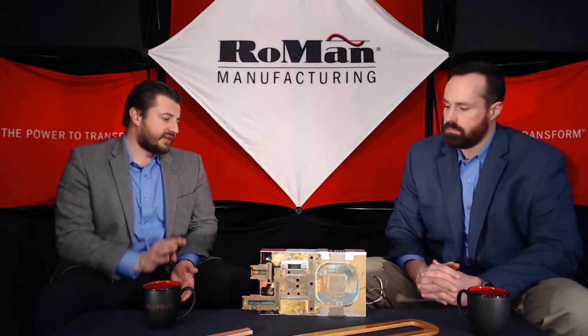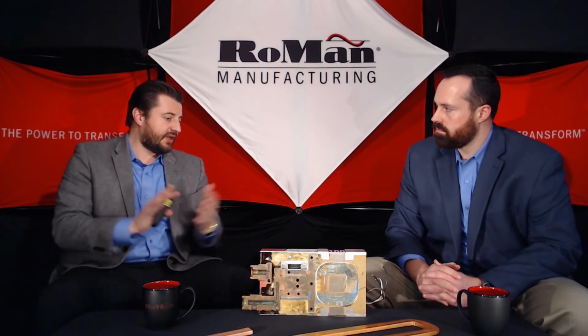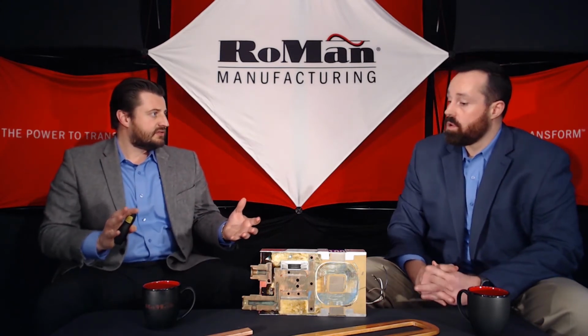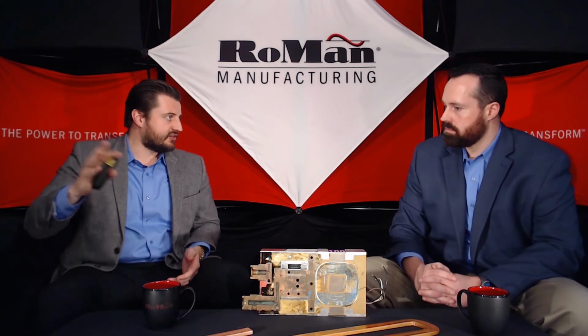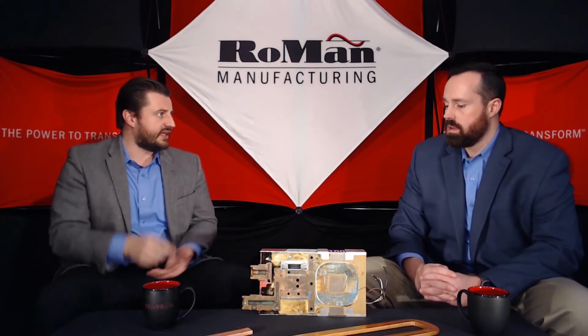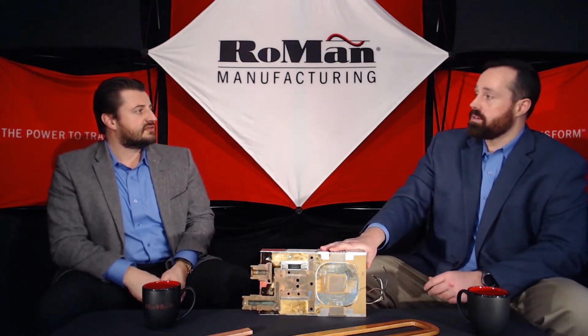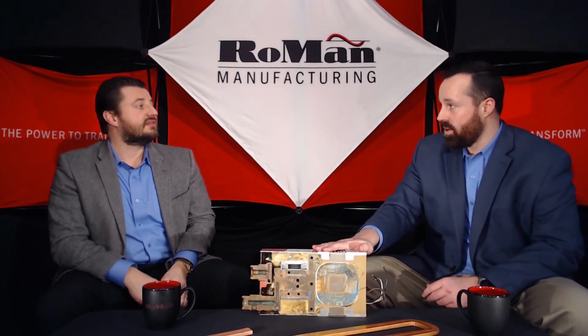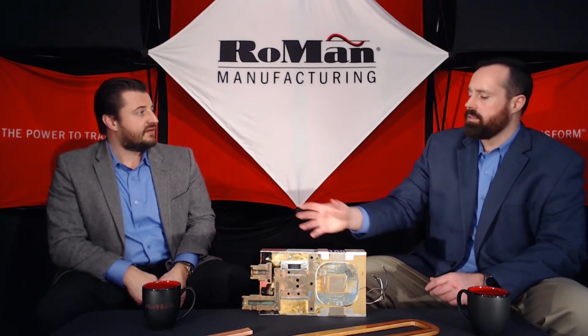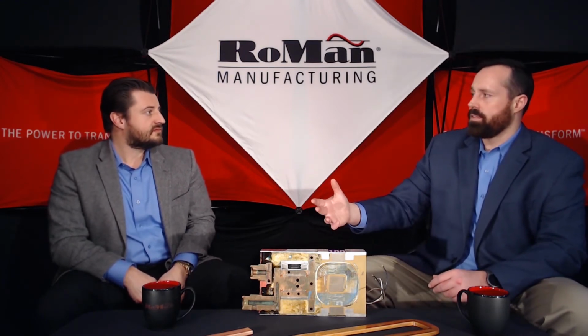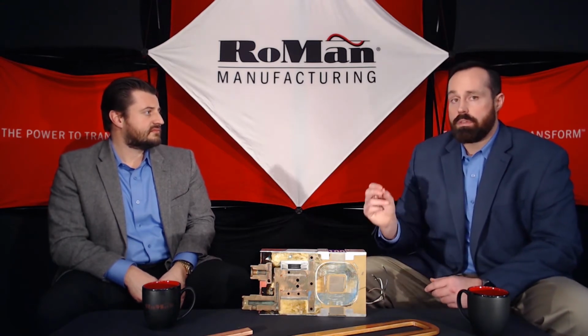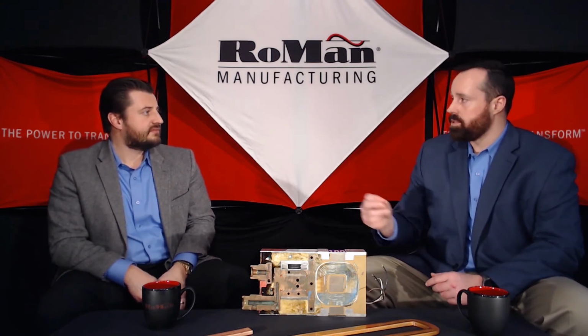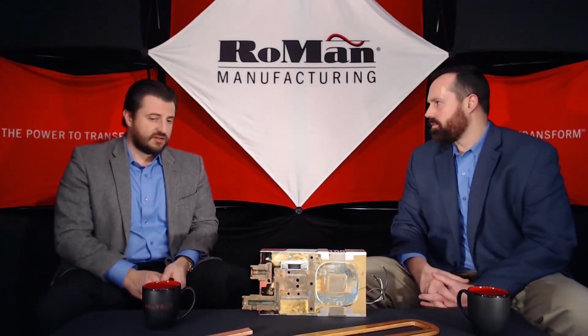Okay. Now, just out of curiosity, how much does that change depending on the size of the transformer? So, does it go to like 10 gallons or 100 gallons, or does it stay pretty close to that? So we make transformers up in the MVAs as well. So we can make very large transformers for very special applications. But even more of our common larger transformers are around the scale of 400 kVA. But still, the water flow remains the same. It's about 1 to 2 gallons depending on the design. A larger transformer doesn't necessarily need more water flow.